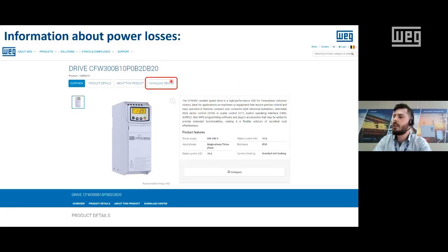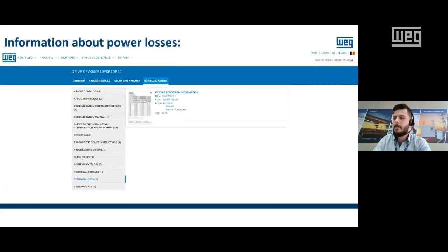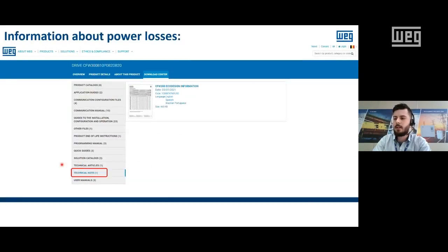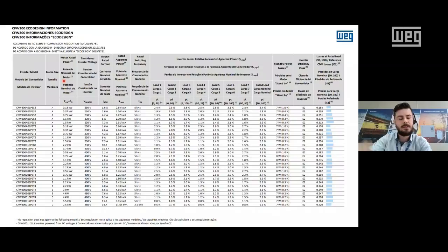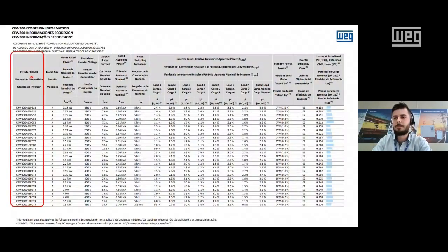And then you can click on Download Center. And then you are going to go to Technical Notes. And you will have this file here, the Ecodesign information. If you click here, you are going to come to a document like this, which is specific to every variable speed drive. And in the first column here, you're going to find the inverter model. And here in the inverter efficiency class, you're going to find the IE class of this drive, where the regulation now just defines IE1 and IE2. So you're going to find all drives to be IE2.